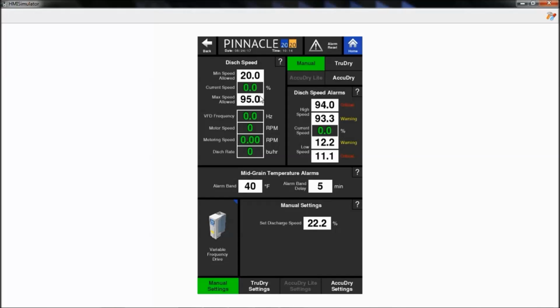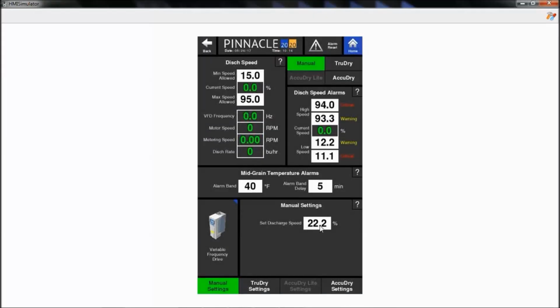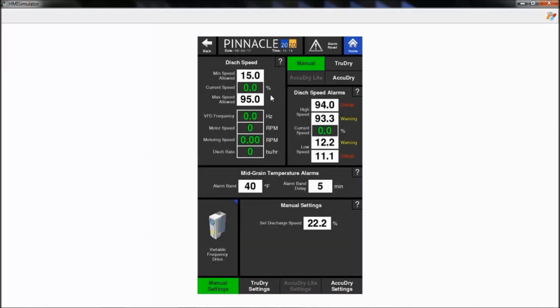These operational set points, it's important to understand the difference between an operational set point and an alarm set point. These values are hard-coded and you cannot run outside of these values. So if I were to try to change my speed outside of this range from 20 to 95, we'll see that my minimum value I can enter is 20 and my maximum value I can enter is 95. If I were to reduce my minimum speed to 15, now when I go to change my discharge speed, I can go from 15 to 95. So where you see something like this, an operational set point, these are hard-coded, it's going to restrict what the dryer can run at. That's different from an alarm setting.